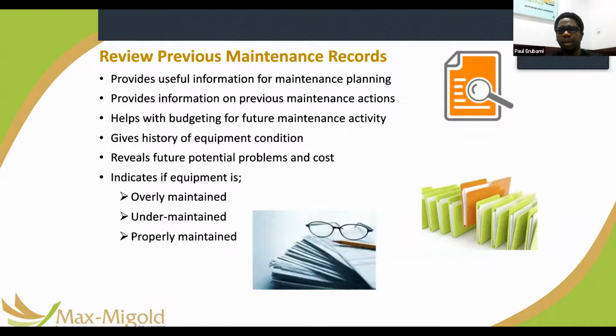And I wasn't surprised the elevators were being epileptic. But if I met them working, I've done a condition assessment, and I did not know that they were installed in the early 60s, for example, neither did I know what kind of maintenance has happened between then and now, how many components have been replaced, how many times the cabling has been changed, the sensors, and so on and so forth, I probably will not be able to envisage when major issues can occur.